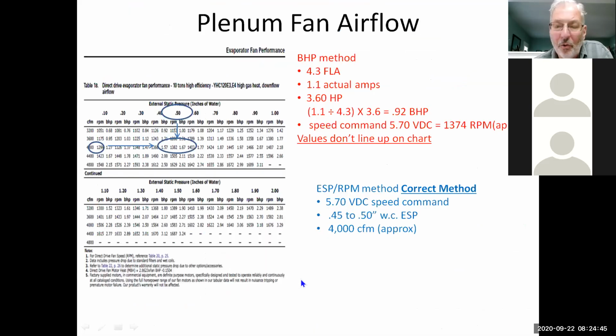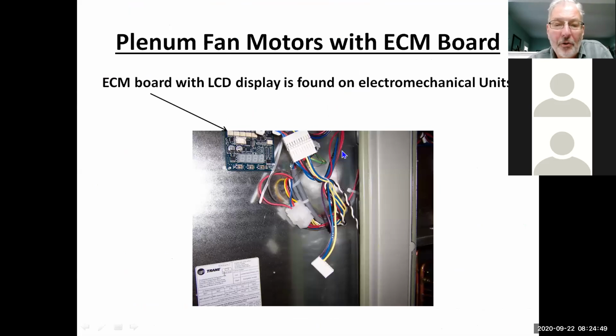And what I do, I'm gonna jump past this one. What I do is I go into, if it's this control right here, I hit the set button and it'll display 5 volts DC, and I hit the plus button until it goes to 6.5 volts DC. Once I get to 6.5 DC, then I hit the set button again for 3 seconds, and that's made my changes. Blower should speed up, and you're all set. That's all there is to setting these motors up.